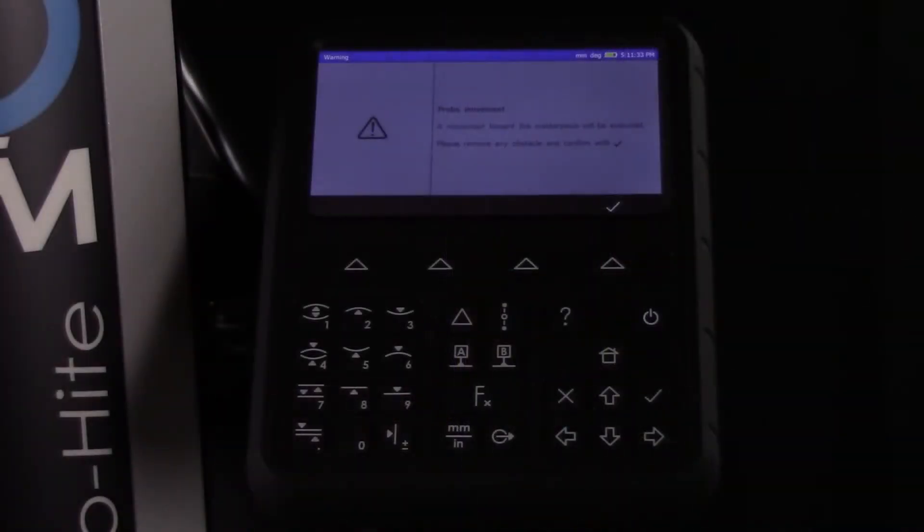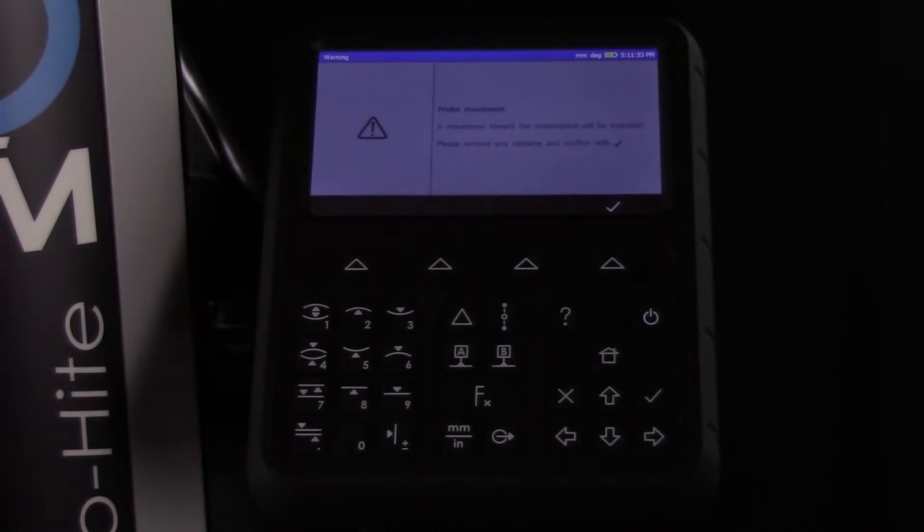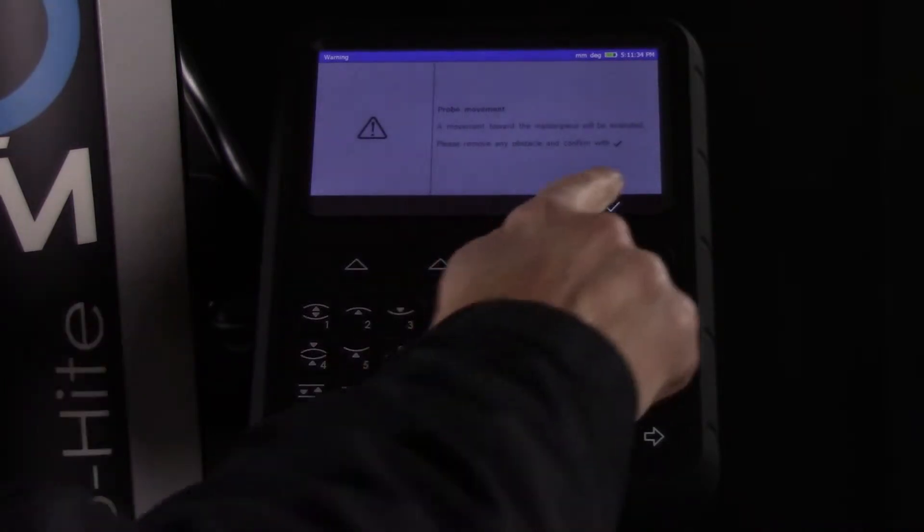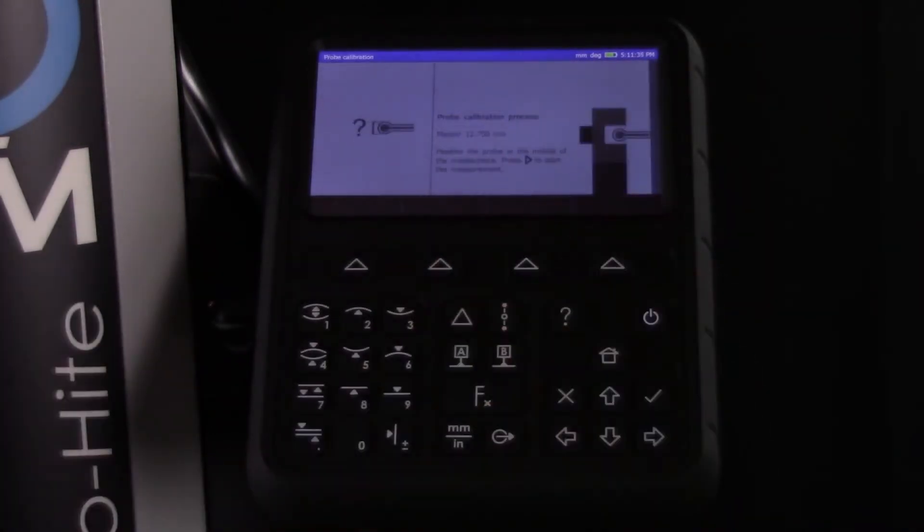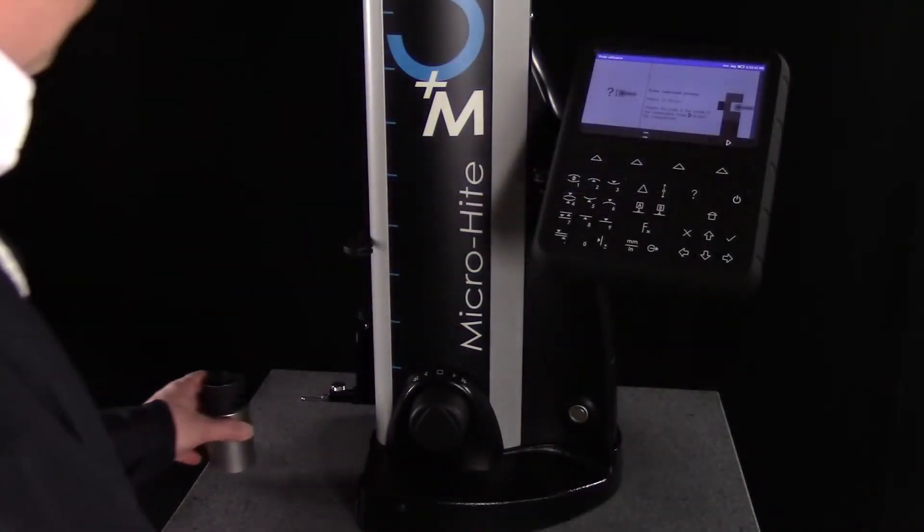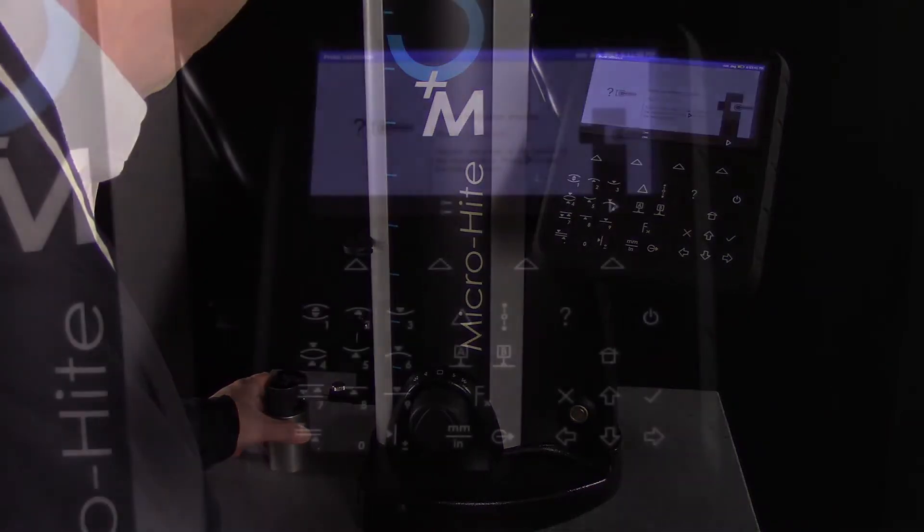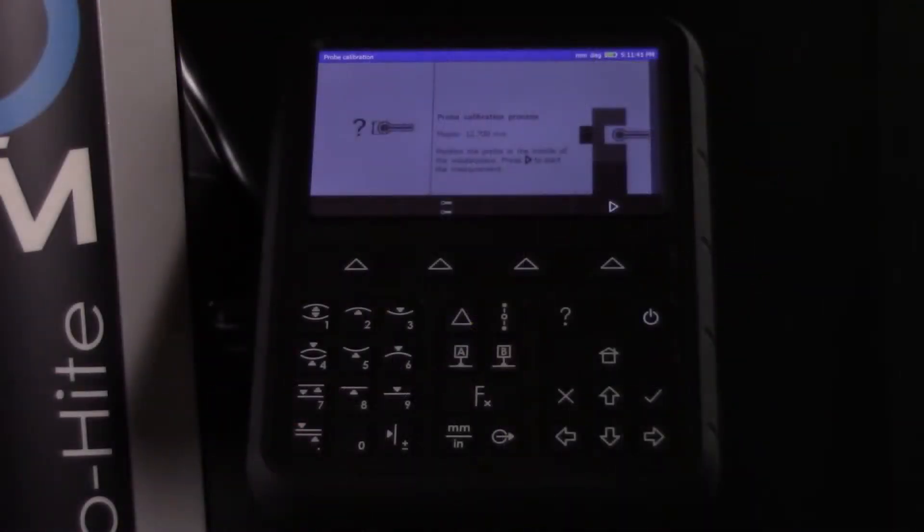Next, the display will indicate that it's time to calibrate the probe using the Masterpiece. Move all other parts away from the probe and position the Masterpiece for calibration. Then, press the right arrow button on the display to begin the calibration sequence.